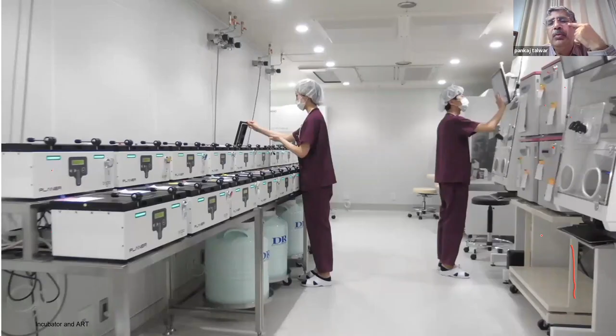Number of incubators in the laboratory, how many should we use? Normally an incubator which is around 150 liters, working on 6% carbon dioxide, we don't use for more than 4 patients per incubator. Not more than 4 patients per incubator. And nowadays we are going towards the level of 1 patient per incubator. But these incubators cost around rupees 6 lakhs. Incubators they have kept here. They're tri-gas incubators. See, so many of them they have kept. These are the CO2 incubators. So the better the lab, the more incubators they will have.